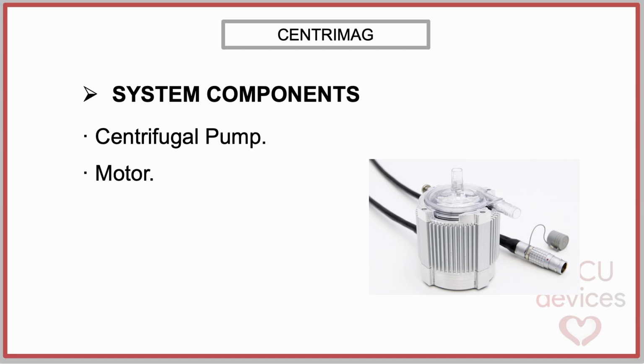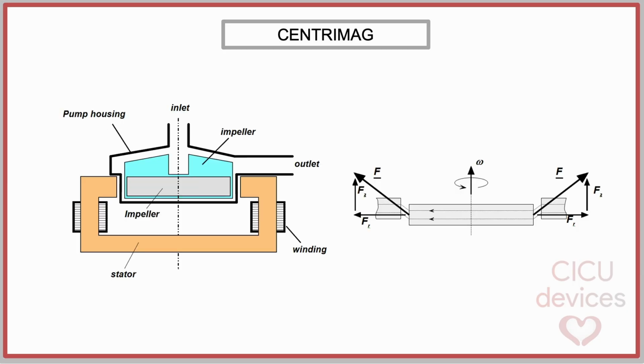The motor magnetically drives the pump rotor. The motor houses the pump and magnetically couples with the rotor inside the disposable pump head, enabling contact-free rotation. This motor generates a controlled rotating magnetic field that interacts with the magnetically levitated rotor housed within the disposable pump head, enabling contact-free transmission of motion.